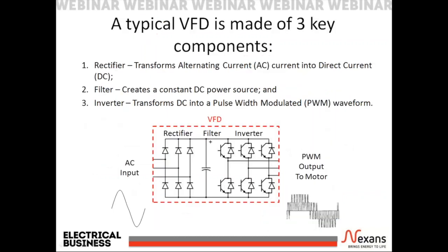A typical VFD is made up of three key components: a rectifier, a DC filter, and an inverter. The rectifier is usually made up of a series of diodes, but could be controlled semiconductors, such as silicon-controlled rectifiers, or SCRs. The DC filter is usually made up of a few inductors and a large grouping of capacitors to smooth out the DC ripple from the rectifier. The inverter is usually made up of high-speed semiconductor switches, such as insulated gate bipolar transistors, IGBTs, allowing the inverter to chop up the DC output.